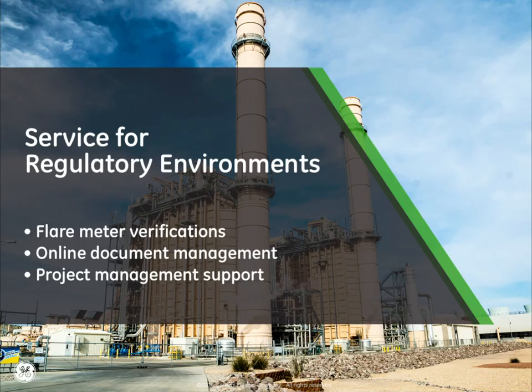In the petrochemical space, new and increasingly stringent regulations continue to affect operators from product and service standpoints. In response, new technologies have been developed to address difficult low-flow accuracy requirements and a need for redundancy. Correspondingly, on the service side, organizations have also evolved to improve flare meter uptime. You'll see this in a variety of areas, and I'll provide a few examples. Industry-proven procedures are now used to account for regulatory verifications and validate flare flow meter operation. Diagnostic tests are performed on meter electronics to certify that OEM accuracy parameters are still intact. Flow simulations are run to ensure that meter performance meets requirements across a wide flow range. Now flows as slow as 0.1 foot per second, and as fast as flaring conditions are accounted for. Lastly, hardware inspections are performed to validate structural integrity, account for any buildup on the transducer probe heads, and adjust for any process changes.